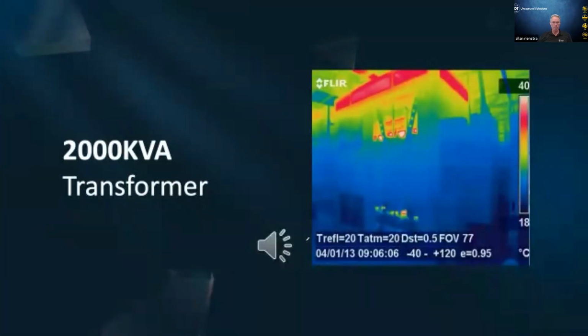Not just the noise from the transformer, but the whole transformer itself was very noisy. And infrared scans showed hot spots as well. So here's a great example of where we combined the power of thermal imaging with ultrasound to not only confirm a diagnosis, but to isolate and localize where the problems might be coming from.